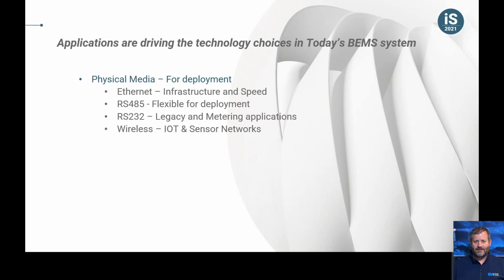So when we look at applications, we sometimes forget to look at the physical media, how they're actually connected together. And maybe in the design portion of your BMS system, we should take more consideration of the physical media, such as Ethernet for the infrastructure and speed, RS-485 for flexibility and deployment, RS-232 for legacy and metering applications, and of course, wireless and the IoT and sensor networks. Pretty much anything with an 802.11 chip in it can now communicate via Modbus or IP back to the central network. And you also see a lot of wireless sensor Zigbee networks.